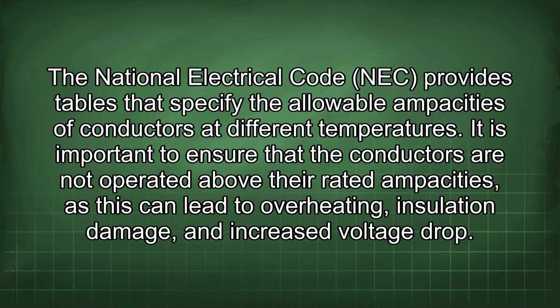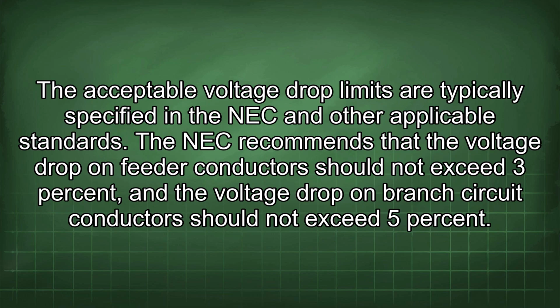The National Electrical Code (NEC) provides tables that specify the allowable ampacities of conductors at different temperatures. It is important to ensure that the conductors are not operated above their rated ampacities, as this can lead to overheating, insulation damage, and increased voltage drop. The acceptable voltage drop limits are typically specified in the NEC and other applicable standards. The NEC recommends that the voltage drop on feeder conductors should not exceed 3%, and the voltage drop on branch circuit conductors should not exceed 5%.